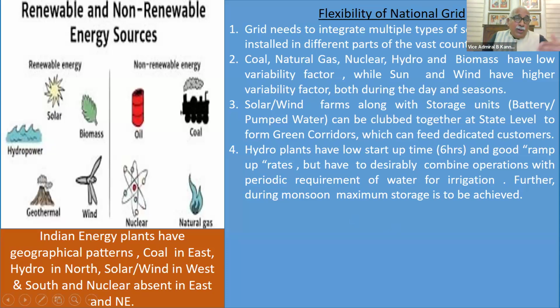But you cannot use hydro power plants the way you want, because their water is supposed to match with agricultural requirements. It has to be periodically assessed to meet the impending agricultural requirement. So there's a limitation on how much power you can take, and how often, from a hydro station, even though it has a good ramp up profile and low startup time.